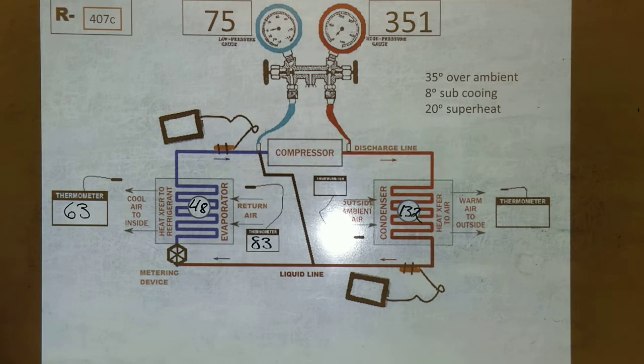Okay, you get it, Felipe? Nope. Come on, get it together. So we got 48 by putting the pressure into the PT chart. And then there's a 35-degree difference from return air to the low side saturation temp. So that's how we got the 83. You get the 63: it's a 20-degree difference from the return air to the supply air.